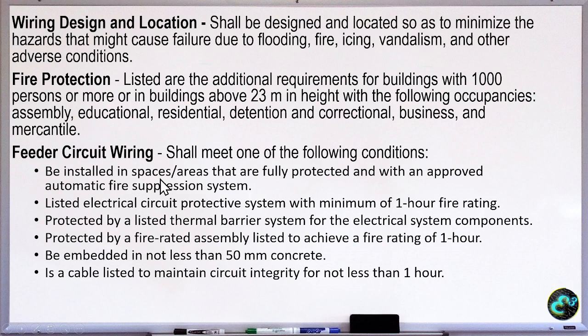Be installed in spaces or areas that are fully protected with an approved automatic fire suppression system. The fire rating is 1 hour, then there is a thermal barrier, and the thermal barrier is also rated 1 hour. Or the system is embedded in not less than 50 mm of concrete. Then the cable is said to maintain circuit integrity of not less than 1 hour.